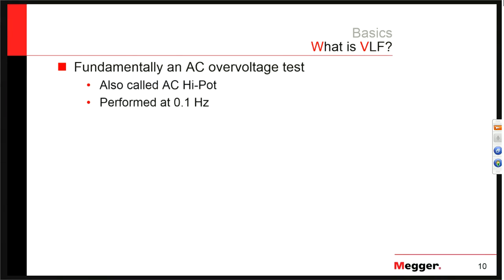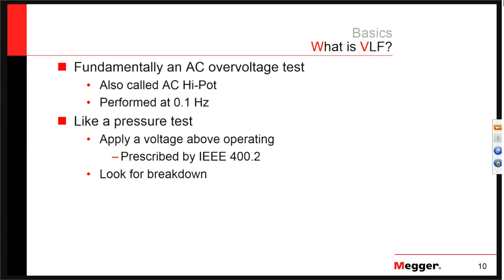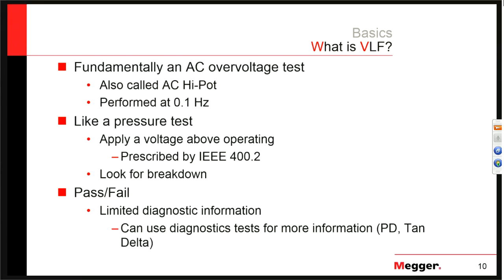What is VLF? Fundamentally, it's an AC overvoltage test or AC high pot performed at 0.1 hertz — like a pressure test. We apply a voltage above operating voltage, all listed in IEEE standard 400.2, and look for a breakdown. The cable will either survive the test and pass, or it'll break down — a simple pass-fail result. VLF technologies can also add measurements and do partial discharge diagnostics or tan-delta diagnostics with the same basic waveform and power supply.